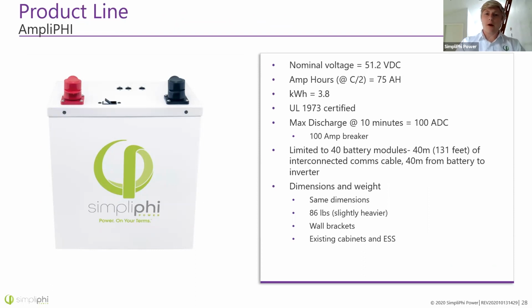Our AmpliPHI battery, this is our newest battery added to the lineup. It's the same basic specifications as the other battery, the 3.8 kilowatt hour battery, so 75 amp hours at 51.2 volts nominal. This is also UL 1973 certified, but it's got a slightly increased max discharge here at 100 amps for 10 minutes.